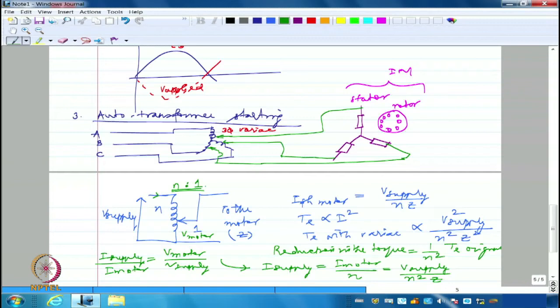So it is very, very similar to star delta starting. If I assume that instead of n:1 I have √3:1, you would not see any difference between the star delta starting and this auto transformer starting. If I assume that I still have the motor winding connected in delta itself, but I'm going to have √3:1 as a variac which is inserted, it will behave exactly similar to a star delta starter, right?